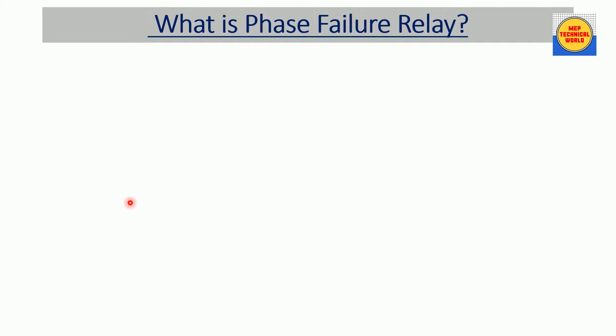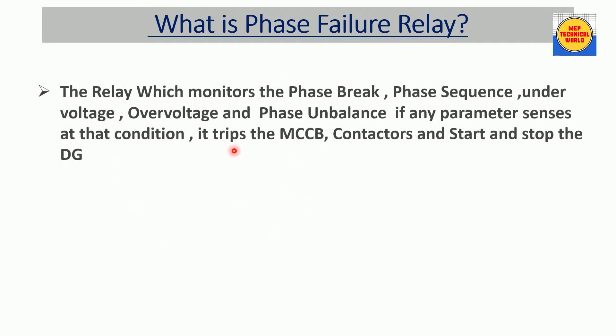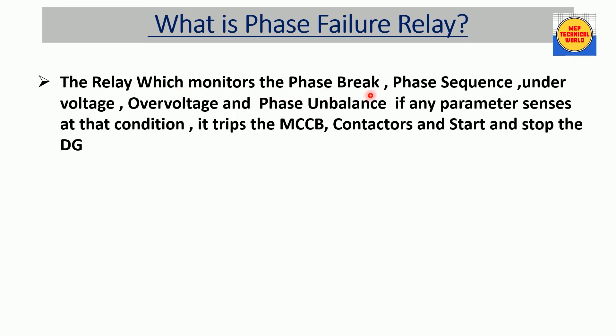So let's start. Basically, what is a phase failure relay? It is the relay which monitors phase break, phase sequence, under-voltage, over-voltage, and phase unbalance. If any parameter changes, it trips the MCCB contactors, and in the case of an ATS panel or AMF panel, it starts and stops the DG (diesel generator).